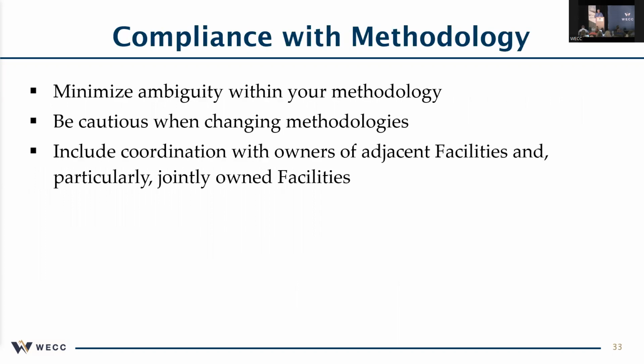The issue of compliance with methodology and the weaknesses we see are, you write your methodology, you look at the standard, and the standard gives you 3 or 4 different ways to establish a rating. You go, good, that's great, that's flexible. You put those in your methodology, but you don't put a preference, such that 2 different engineers on your own staff can go look at your own methodology. One guy can say, I'm going to use an IEEE standard from whatever year. The other guy says, I'm going to use a nameplate. You can come up with 2 different numbers.